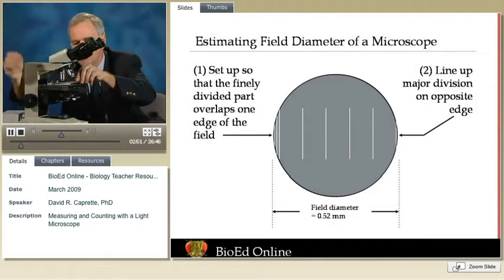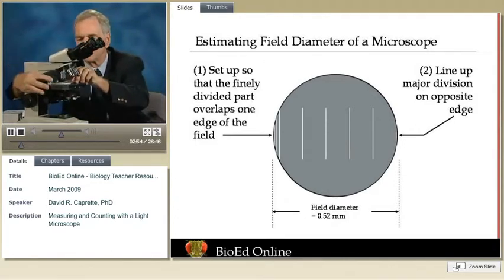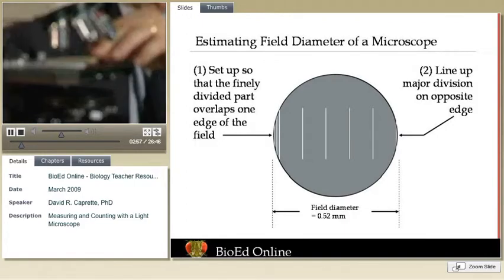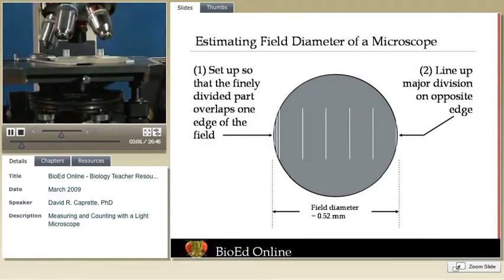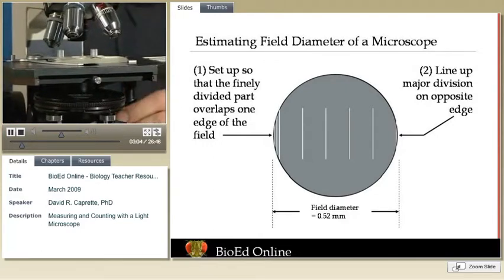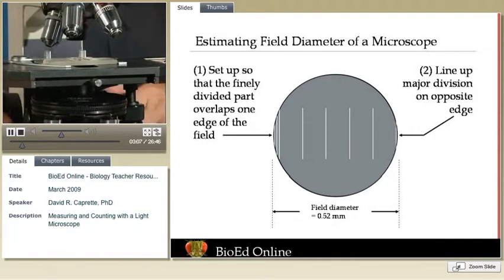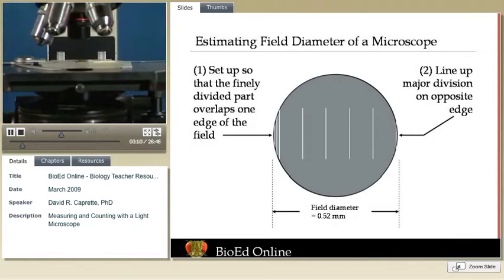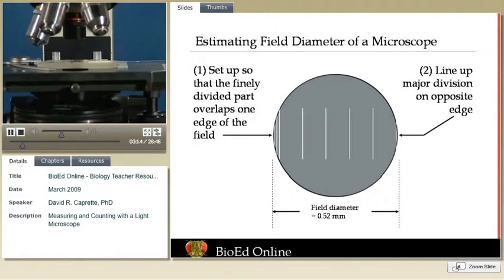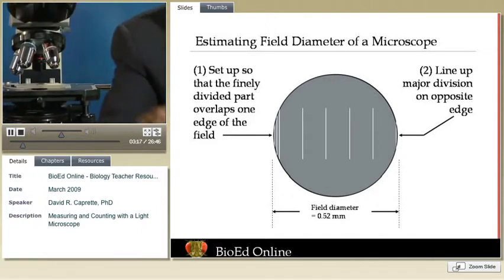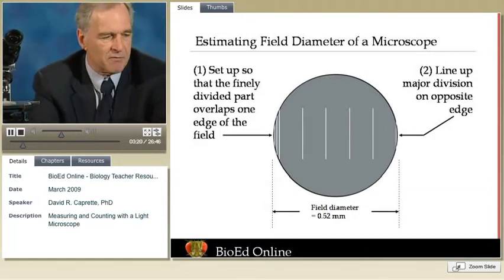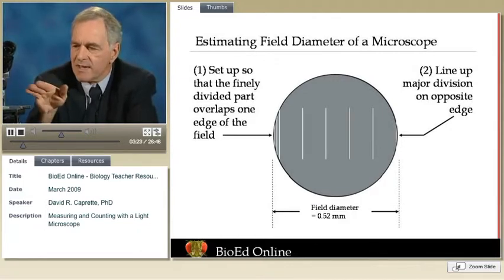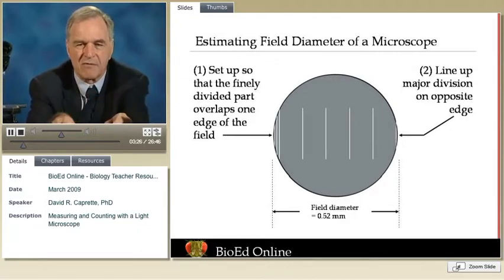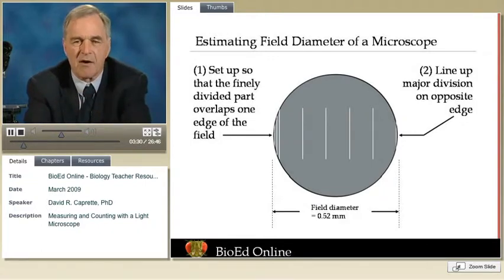To use one, we place the micrometer on the microscope stage. Keep in mind now that because it's a much thicker piece of glass, the focal distance has to be a little larger. We have to lower the stage more than we would with a conventional slide. And we can focus on the scale. Now, once we're focused on the scale, one useful method of calibration is to calibrate the field diameter itself. With the field diameter estimated, we can estimate the surface area through which the light is coming, that is, the area of our field of view, and we can use the field diameter to count, say, the number of objects per unit area on a surface.